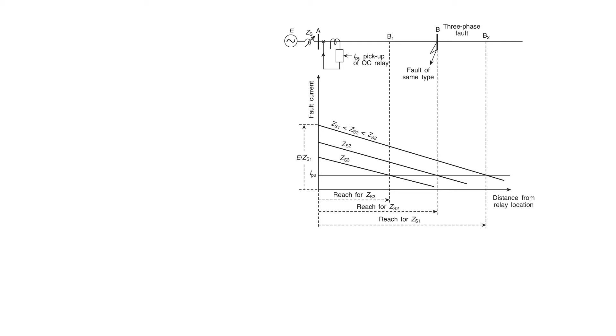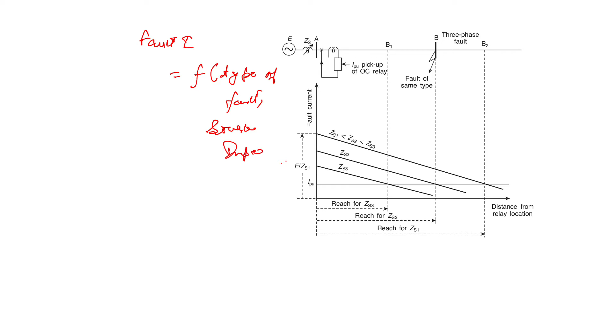Thus, we see that the fault current is a function of the type of fault and the source impedance. This is clear from these two diagrams. These are variable, and they keep on changing. So we must look for a relay whose reach does not depend upon the actual magnitude of the fault current. The search for this relay leads to the type of relay known as the distance relay, which does not depend upon the actual magnitude of the fault current, but on the ratio of the voltage at the relay location and the fault current.